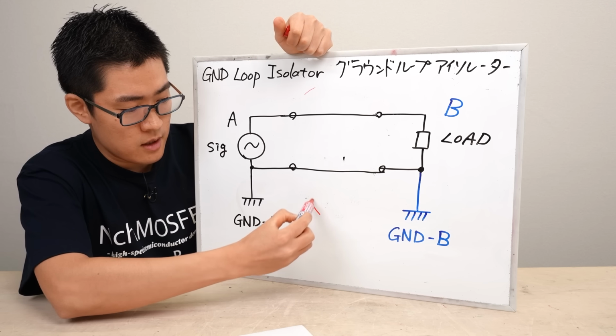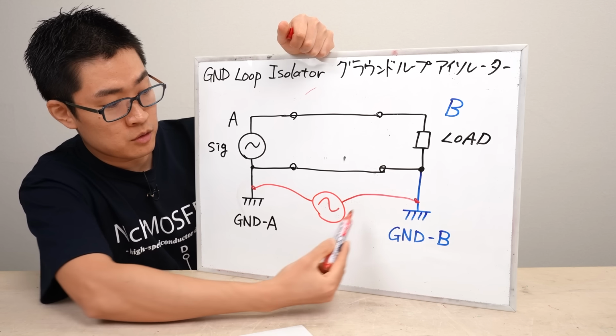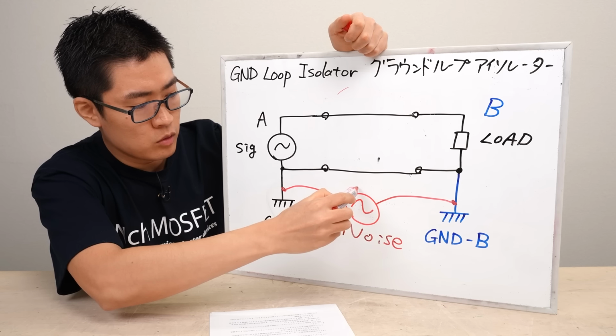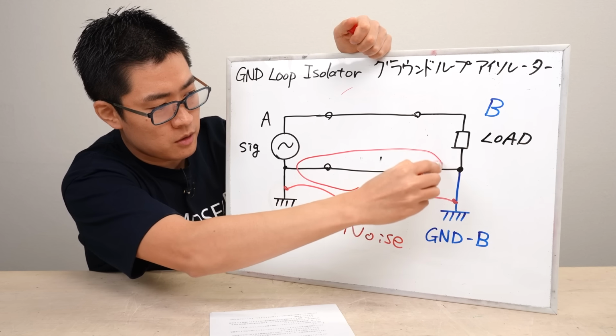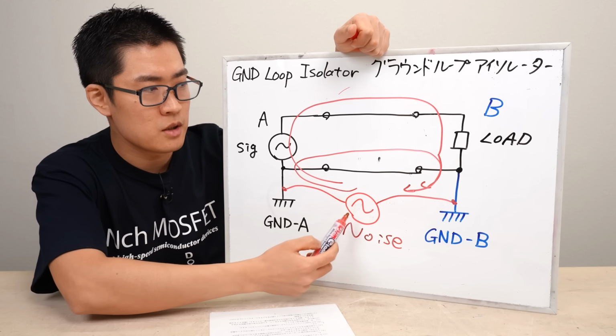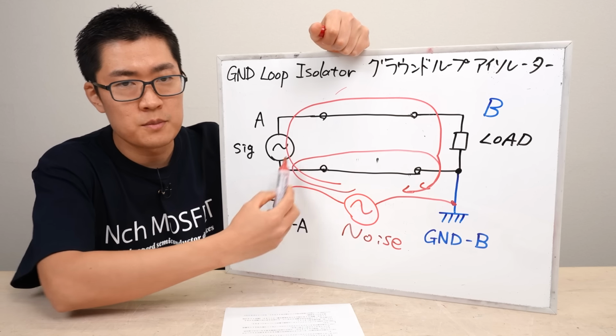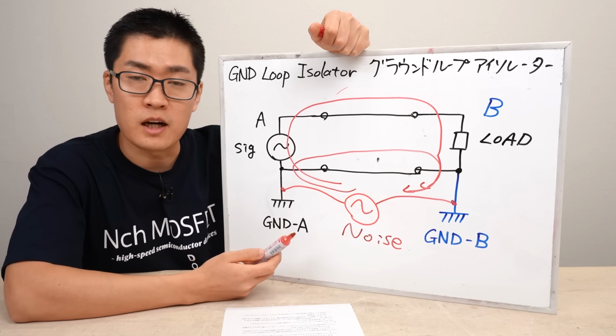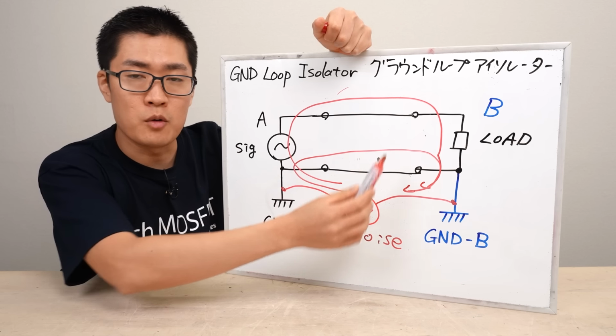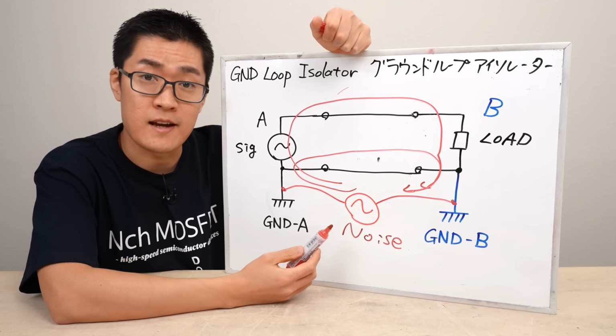Now, let's assume there is some unknown source of noise connected between ground A and ground B. In this case, a noise loop is formed along this path, and as a result, the noise is transmitted to device B. Although simply having a ground loop does not necessarily mean that noise will always occur, under certain conditions it can sometimes cause problems like this.